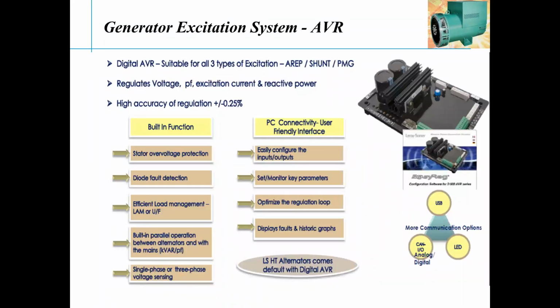And this is what the AVR looks like, a digital AVR, where the digital AVR has 3 types that can be used for all, thanks to the technology, whereas the earlier analog AVR could be used for certain parameters and it should have a variant. Thanks to the digital technology, today we play with the mobile, whether it is a Samsung or an iPhone or whatever it is, in a touch you can do everything. The same technology is put in this digital excitation AVR. And of course, the designers are so smart to give everything, all 3 in 1, whether it is an AREP winding or a shunt winding or a PMG. This digital AVR, any make, can give that excitation system and controlling.